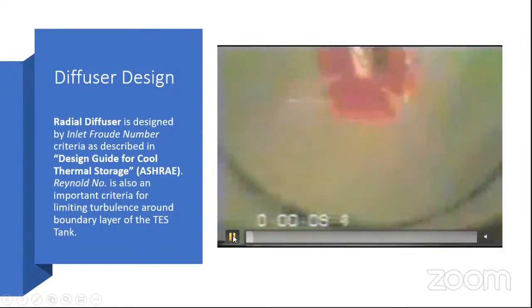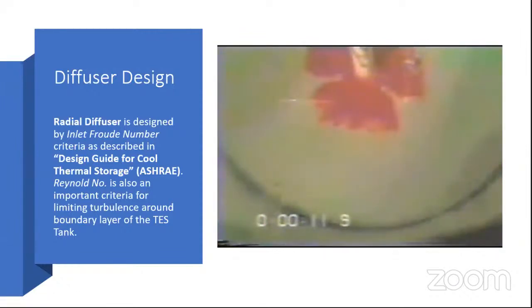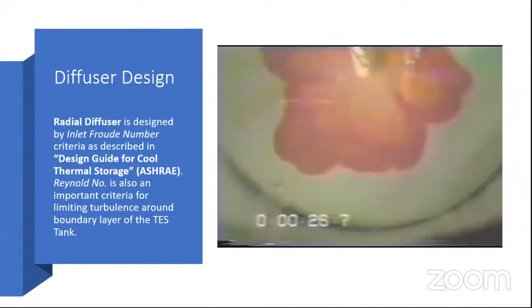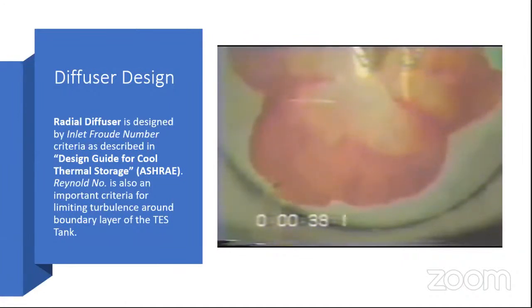Now, I could show you a video here in which you see this. Assume this red fluid to be the warm return water that is coming back inside the tank. The idea is to release the fluid inside the tank with a very low momentum, so that it loses its momentum before reaching the wall of the tank. That is what leads to laminar flow across the tank, and that is what helps the stratification to happen.